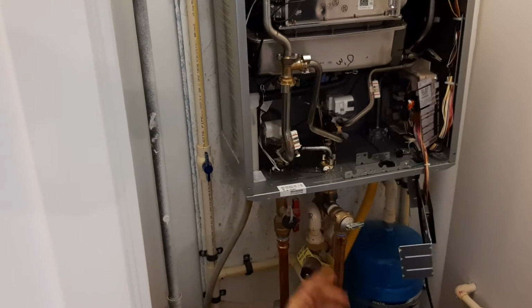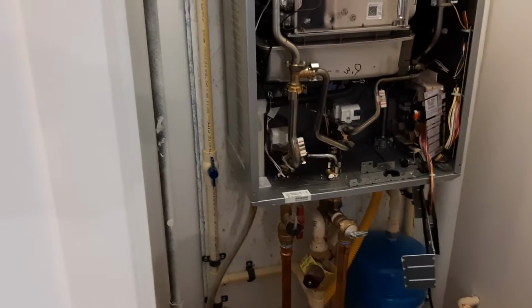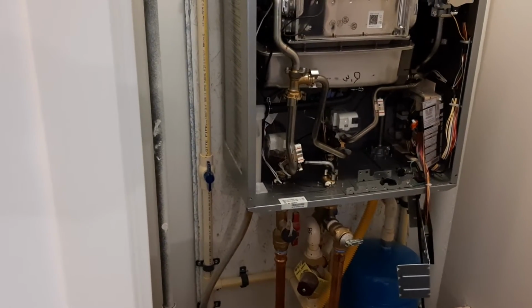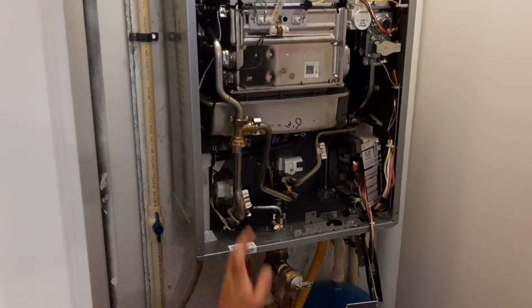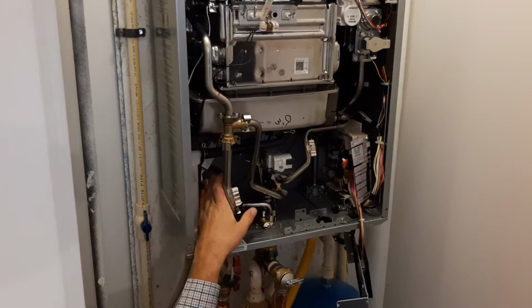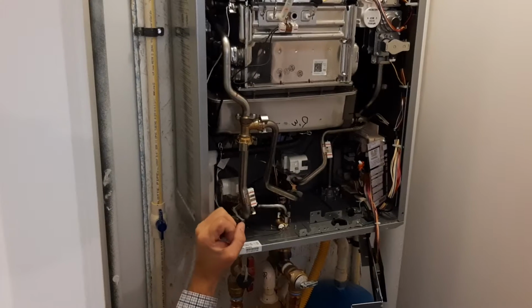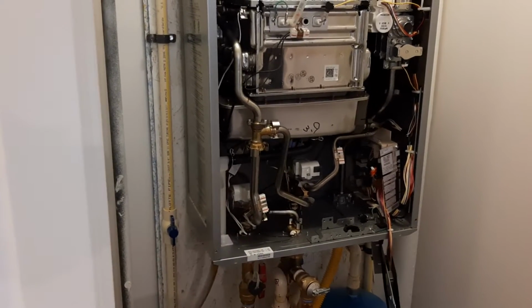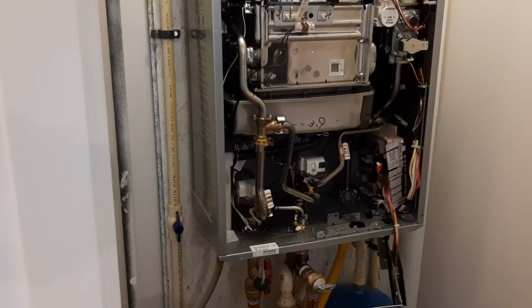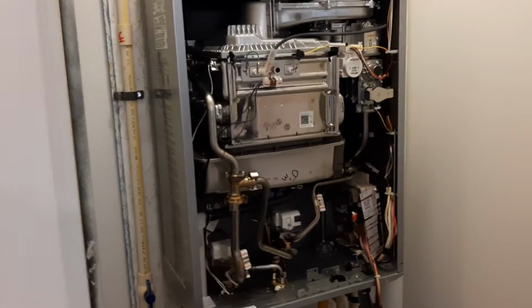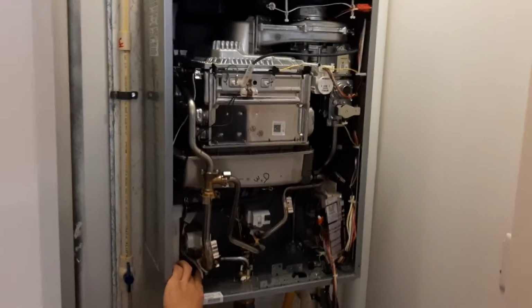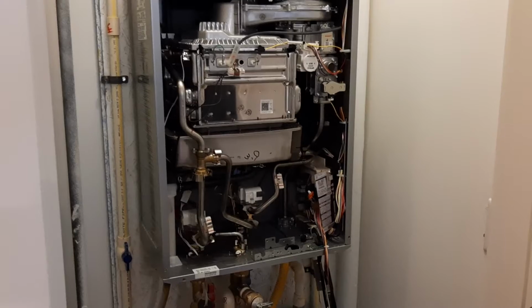So these units can do about 4 gallons a minute. If a homeowner turned everything on in their unit and tried to draw 5 gallons a minute, the unit's going to say, I can't heat 5 gallons. So instead of giving them cold water, I'm going to throttle that flow down and only give them 4. So the end user is going to see a little bit of a pressure drop, but they're always going to have hot water. So again, that's why this is so important, because the unit's always trying to make set point right at this sensor.